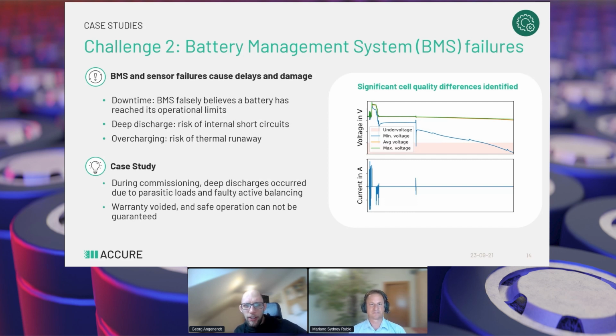On the right-hand side, again, you see a case study. We found that at one system, deep discharge already occurred during commissioning due to parasitic loads and faulty active balancing. This meant the warranty was voided during commissioning, and safe operation could not be guaranteed afterward. This is why it's really important to check all battery parameters during the commissioning phase.